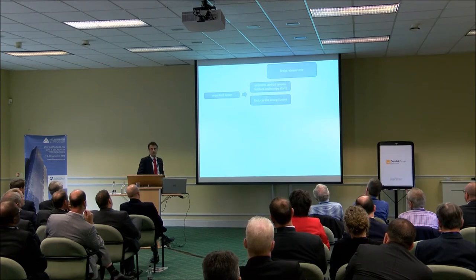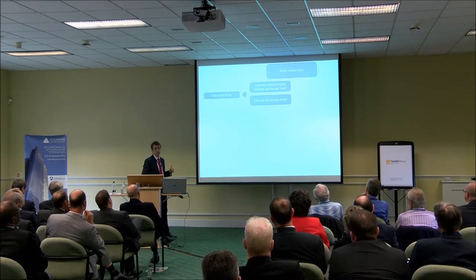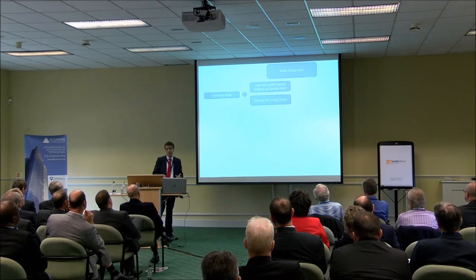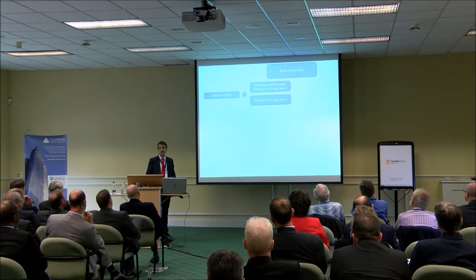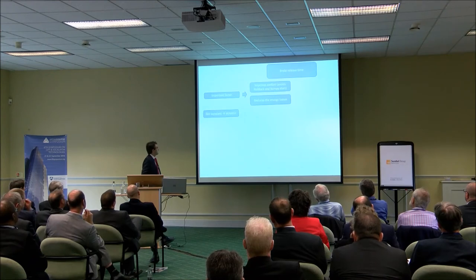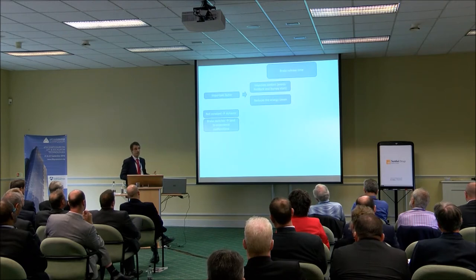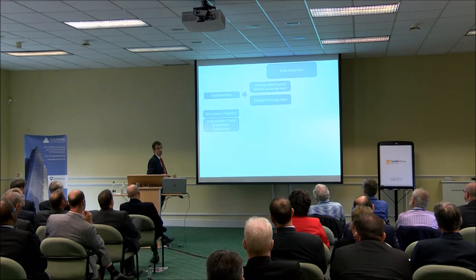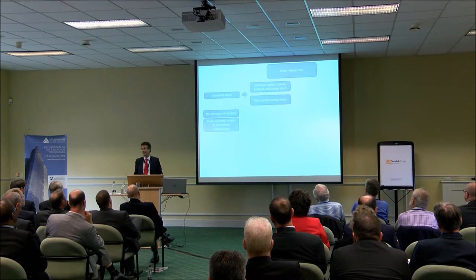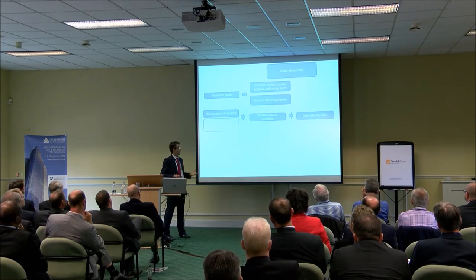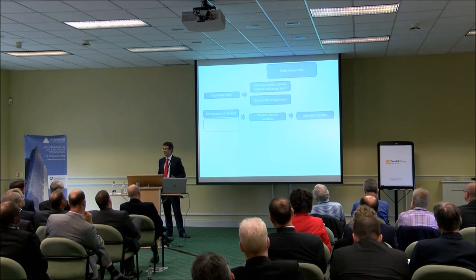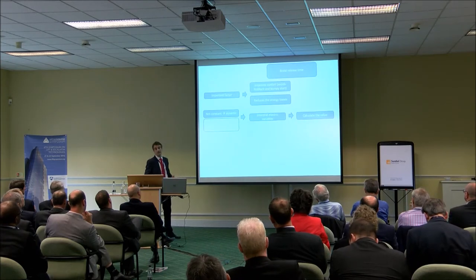The brake release time is an important factor, firstly because we can reduce energy losses, and because it helps to improve the comfort of the journey — we can avoid rollback effects and bumpy starts. This time is not constant; it's dynamic. Traditionally we can use the brake switches to control this time, but unless they are inductive sensors they tend to malfunction. So we suggest interpreting electric variables coming from the frequency inverter and the control panel to calculate this value in real time.